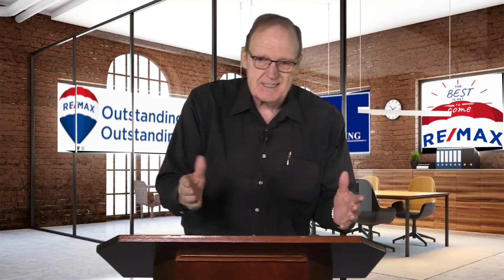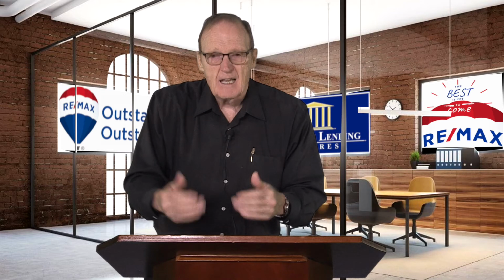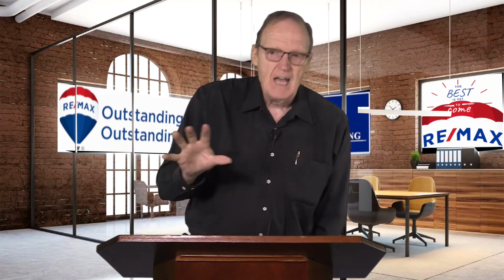You can take a look. That's hard to tell, but certainly if it's paneling, you know you've got a problem. Also, you need solid core exit doors, not between the bedroom and the hallway within the unit, but if the unit exits onto a common stairwell or hallway, then that door needs to be solid core, fire rated with a self-closing device, and the trim around it needs to be fire rated solid. So you need to take a look at it. You can tell certainly whether there's a self-closing device on the door and whether the door is hollow core or solid core. It gives you a rough idea about these sort of things.